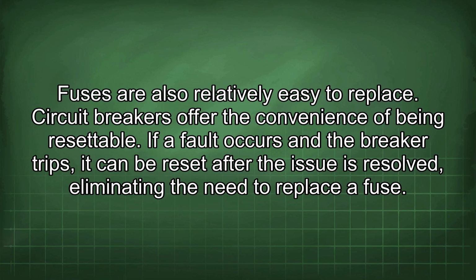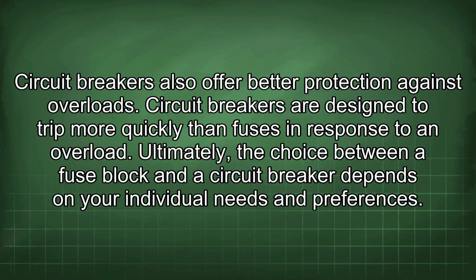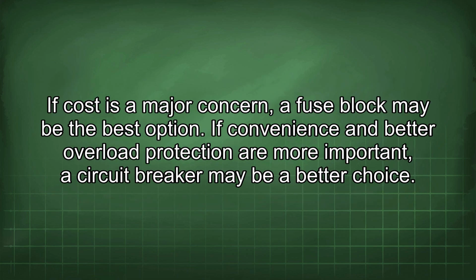Circuit breakers offer the convenience of being resettable. If a fault occurs and the breaker trips, it can be reset after the issue is resolved, eliminating the need to replace the fuse. Circuit breakers also offer better protection against overloads. Circuit breakers are designed to trip more quickly than fuses in response to an overload. Ultimately, the choice between a fuse block and a circuit breaker depends on your individual needs and preferences. If cost is a major concern, a fuse block may be the best option. If convenience and better overload protection are more important, a circuit breaker may be a better choice.